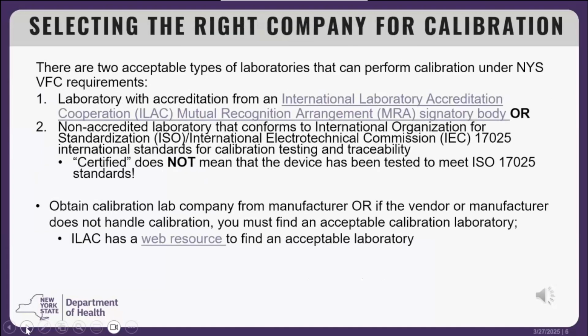There are 2 types of laboratories that can perform acceptable calibration under New York State VFC requirements. The first is a laboratory with accreditation from an International Laboratory Accreditation Cooperation or ILAC Mutual Recognition Arrangement or MRA signatory body. Calibration testing and traceability that is performed by a laboratory with accreditation from an ILAC MRA signatory body assures the user that testing performed meets the appropriate standards. It is also acceptable for a non-accredited laboratory to perform the calibration as long as they state that they adhere to ISO 17025, which is the International Organization for Standardization's general requirements for the competence of testing and calibration laboratories.